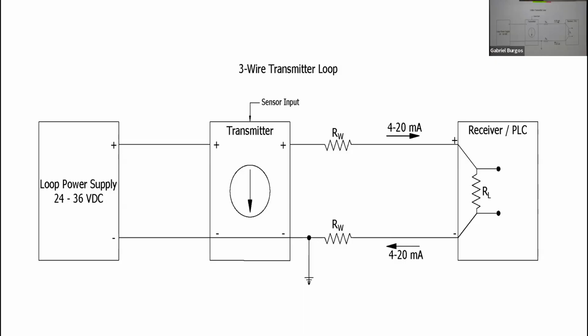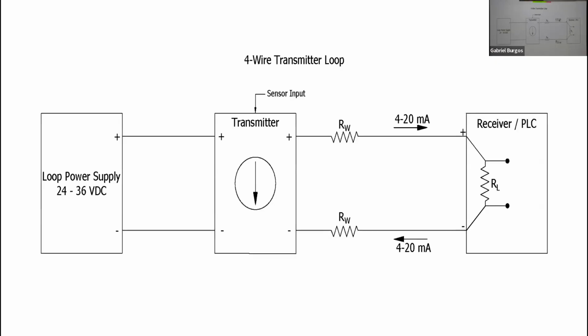Okay? Now, 4-wire transmitter. Here we see that it's kind of a hybrid between the 3-wire and the 2-wire. As you can see, the power supply is completely isolated from the loop. The loop portion is still the 2 wires, but it's a 4-wire unit.